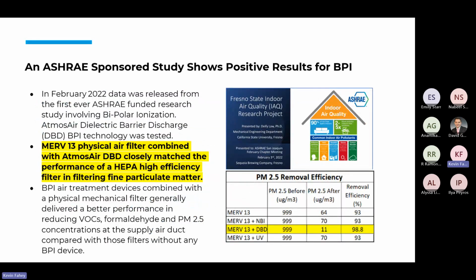The study I mentioned earlier was done by ASHRAE's chapter in San Joaquin, California, where they've historically had a fair amount of wildfires, and are concerned with the particles that are coming inside of facilities as a result of wildfires. So this is the combined, layered effect of different technologies with MERV 13 filters that they did a study on. And they did it with PM 2.5 particulate size, a MERV 13 filter.